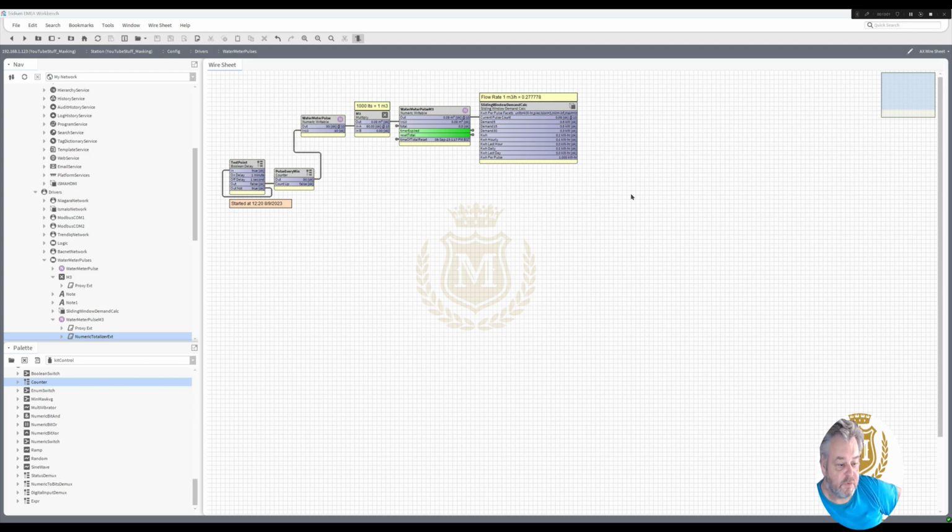So just to give you a view what's happening at the moment. We're now in 90 pulses. So that's 0.09 meters cubed. And we haven't got anything on the total yet that we put in there, which we wouldn't do because it's hourly. And we are getting 0.1 at the moment in our sliding window demand calculator.